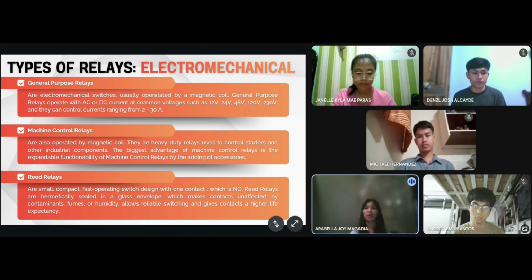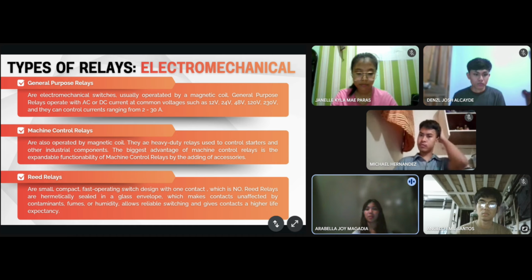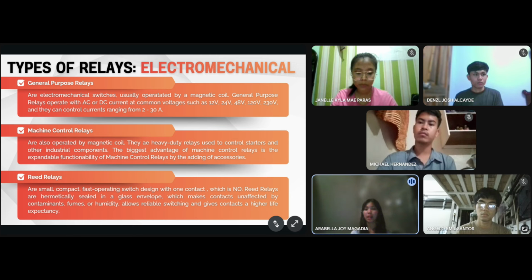Now let's move on to the different types of electromechanical relays. There are actually several types, but for now we'll focus on the three most common ones: general purpose relays, machine control relays, and reed relays. Let's start with the general purpose relays. These are the most commonly used type. They are electromechanical switches that operate using a magnetic coil, meaning once current flows through the coil, a magnetic field is created, which then opens or closes the circuit.